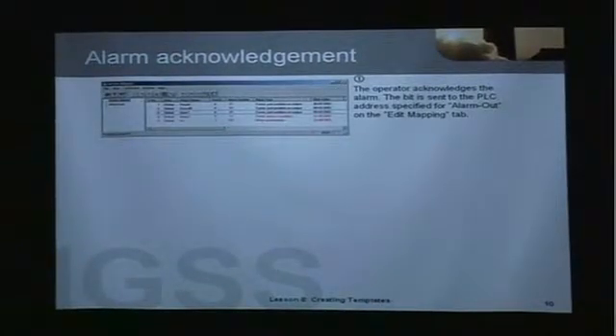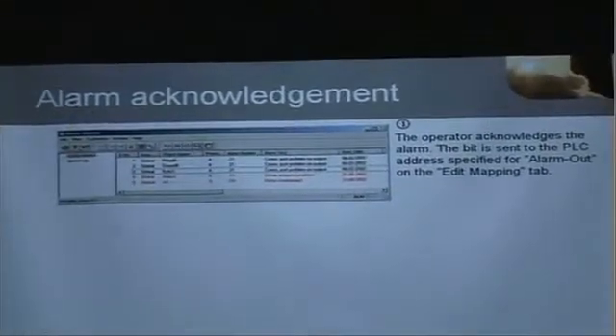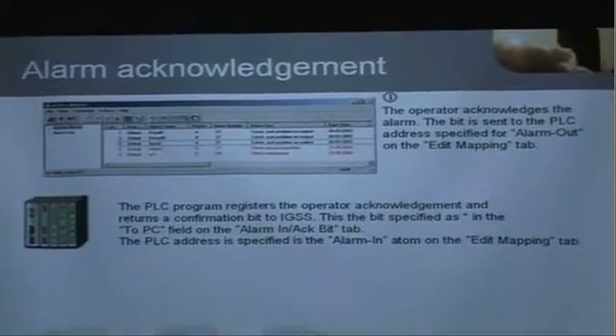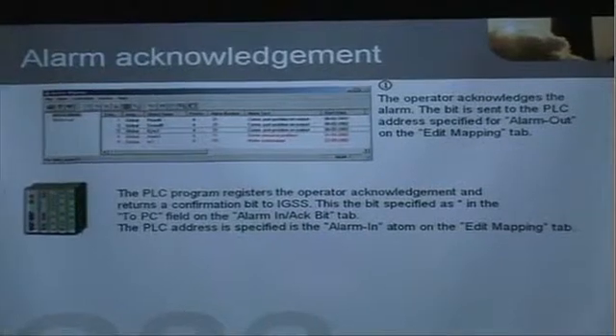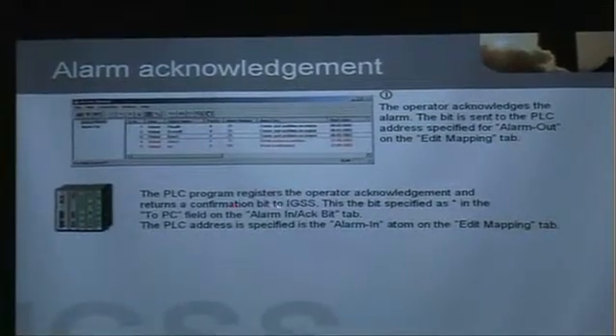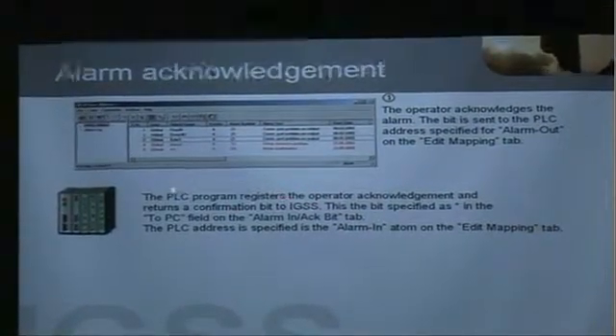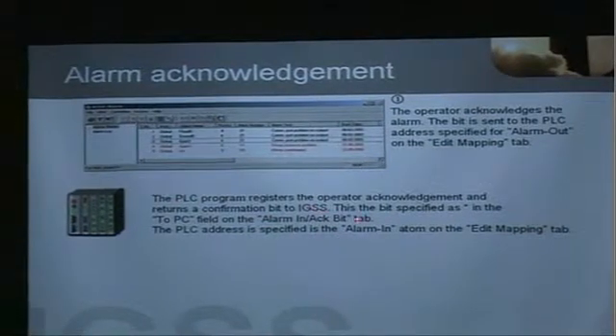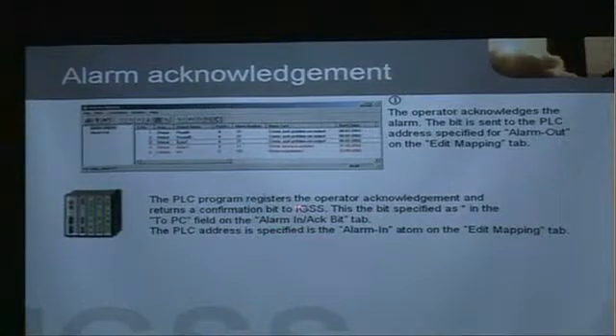Alarm acknowledgement: when the alarm comes into the alarm list, the operator must acknowledge the alarm, and when he does that, a bit is sent to the PLC. We specify the address on the edit mapping tab. When the bit is received by the PLC, the PLC program must register this bit and return a confirmation bit to IGSS. This bit is specified also on the Alarm In/Ack Bit tab.